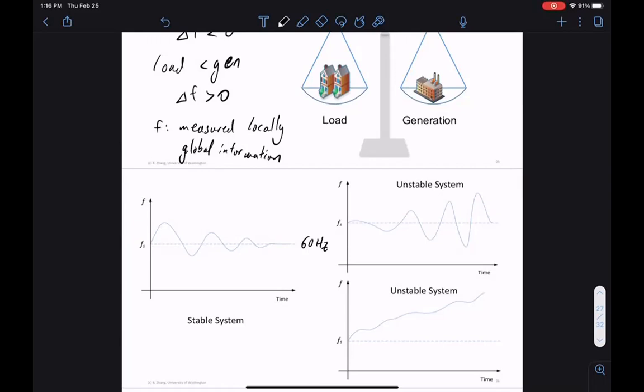The open question in a microgrid, or a system with low inertia, is this: people say low inertia is bad because we're doing this frequency response droop control. We adopt this rule, and if inertia goes down, the control rule doesn't work so well. But if you have a lot of electronics, nobody said this is the rule you have to use. You can use whatever rule you want. Who said you have to act like an AC generator? You have complete freedom in design, and it's unclear whether pretending to be an AC generator is optimal in any sense. That we don't know.